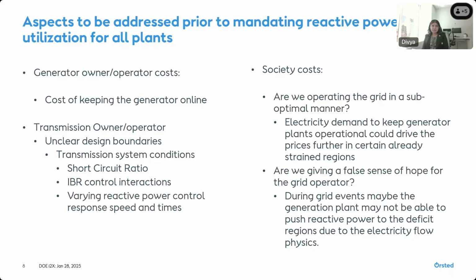Alex did a fantastic job going over some of the control interactions and slow oscillations seen in the ERCOT grid. It's super important to understand what the controls were tuned for, what short circuit level, what the response time was, what the speed of these controls was, so we know if this would be appropriate for a certain condition. Accounting for different response speeds and control response times is critical in ensuring these are the most effective ways of providing reactive power and voltage support to the transmission grid.